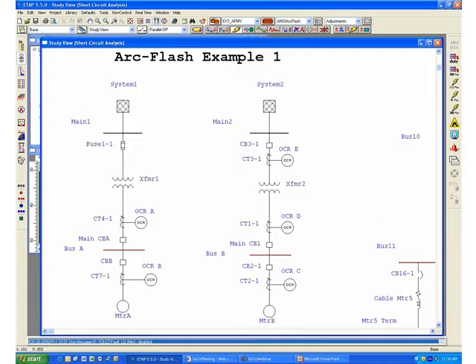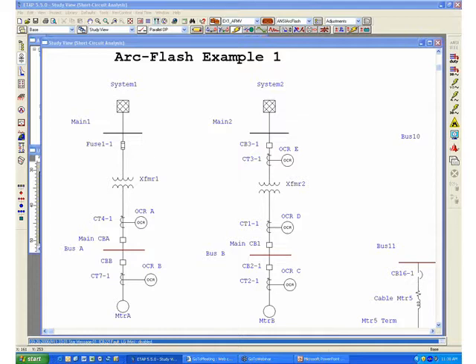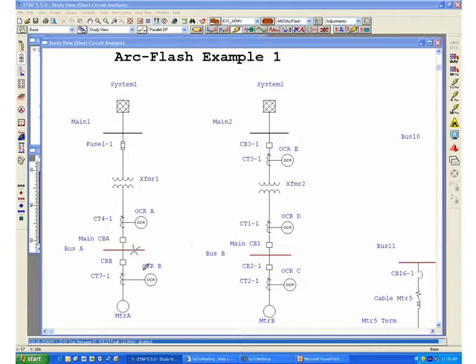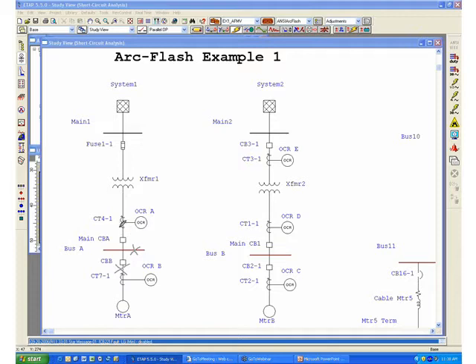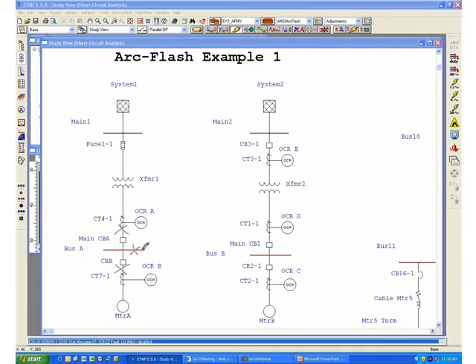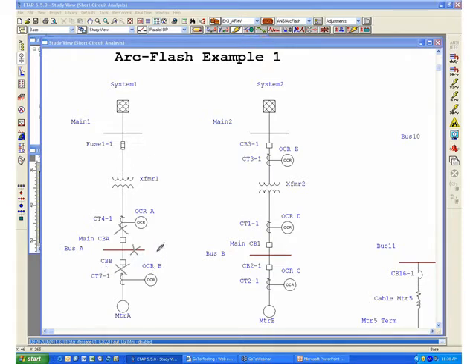I can automatically see that I need to calculate the incident energy that could be released at different locations in the program. The program will automatically give me results for a fault on the bus itself, for a fault on the load side protective devices, or for faults on the line side of the main source PD. By simply placing a fault on the bus, the program will give me three sets of values for incident energy or three possible scenarios, and this will actually reduce the amount of work that you have to do in order to find the most conservative amount of incident energy that could be released in the event of a fault anywhere on this secondary side equipment of this transformer.